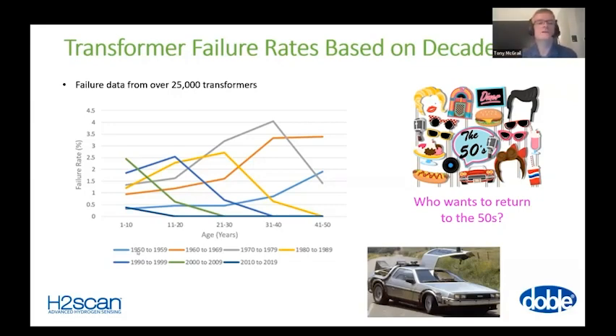There's a light blue line towards the bottom of the chart, showing transformers from an earlier vintage. There isn't much infant mortality, but over decades there's a rise in that failure rate, still rising at 40 plus years old. For the next decade in orange, the 1960 to 69 vintage, the first 10 years show a failure rate of about 1%, then it rises in the next 10 years, and rises again, as if that blue line has been shifted to the left. Then the 1970s, the gray line, shows the same pattern: a rise in the first 10 years, then the next 10 years, and so on. So what we're seeing is that the unreliability seems to be coming in earlier.